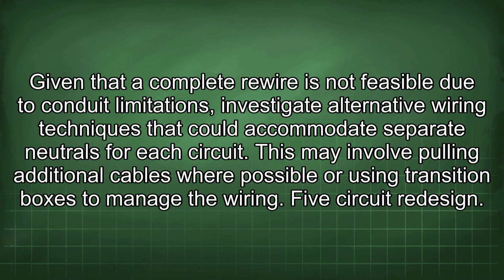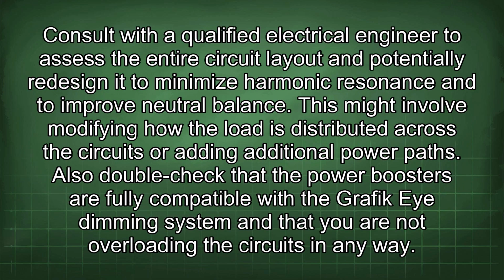5. Circuit redesign. Consult with a qualified electrical engineer to assess the entire circuit layout and potentially redesign it to minimize harmonic resonance and to improve neutral balance. This might involve modifying how the load is distributed across the circuits or adding additional power paths. Also double-check that the power boosters are fully compatible with the Grafik Eye dimming system and that you are not overloading the circuits in any way.